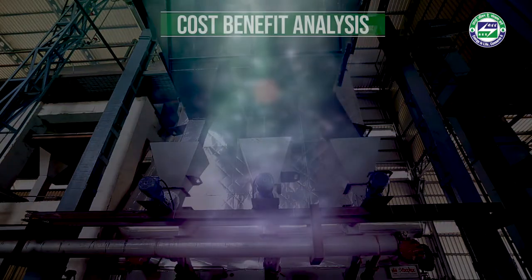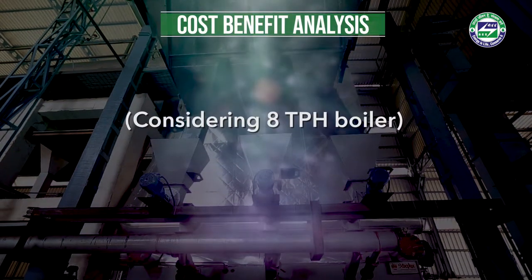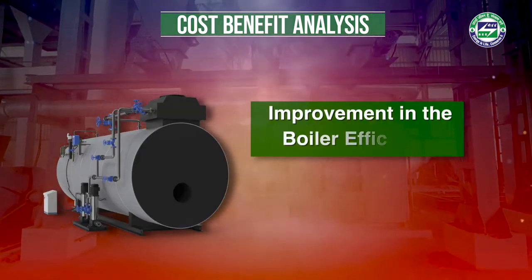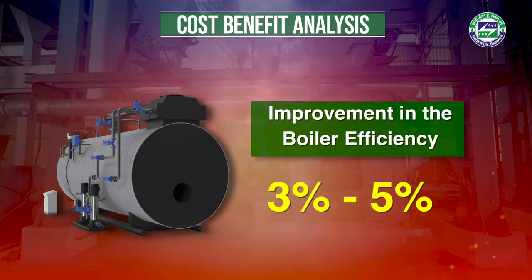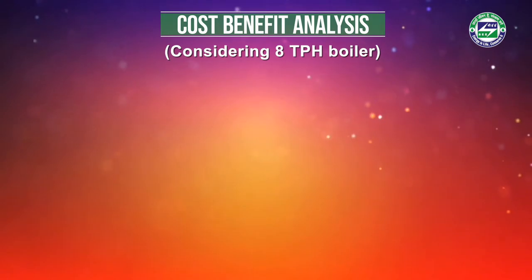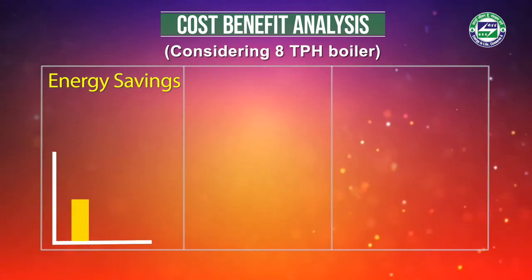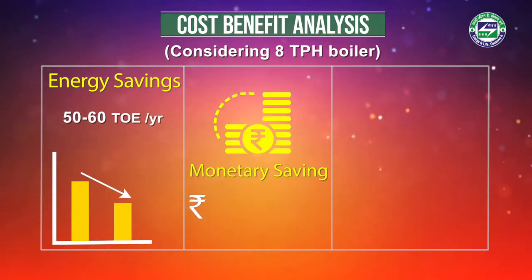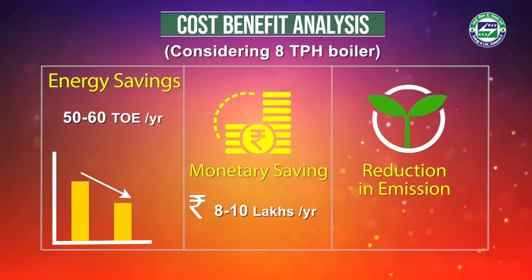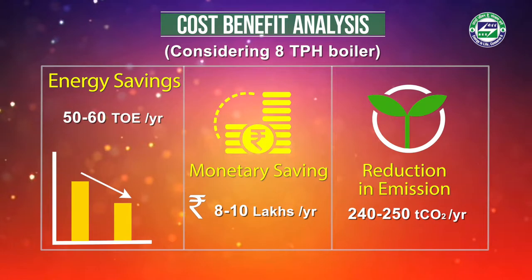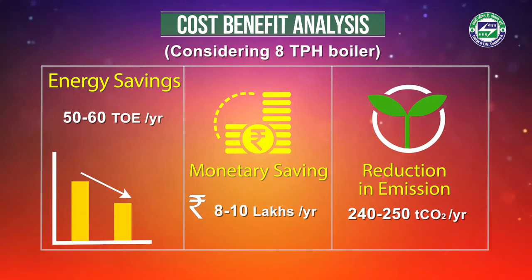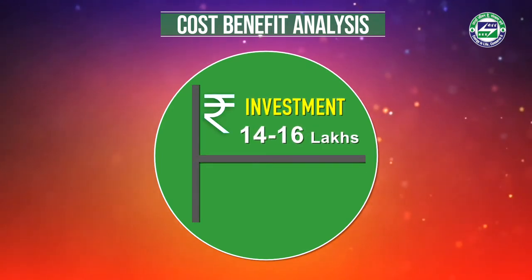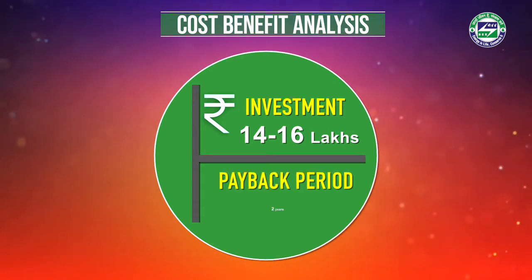To understand the cost-benefit analysis, consider an 8 TPH boiler. The installation of the system will lead to an improvement in boiler efficiency by 3–5%. For an 8 TPH boiler, this leads to a saving of 50–60 tons of oil equivalent of energy, monetary savings of Rs. 8–10 lakhs, and GHG emission reduction of 240 to 250 tons of carbon dioxide annually. The investment required is Rs. 14–16 lakhs, which can be recovered within a period of two years.